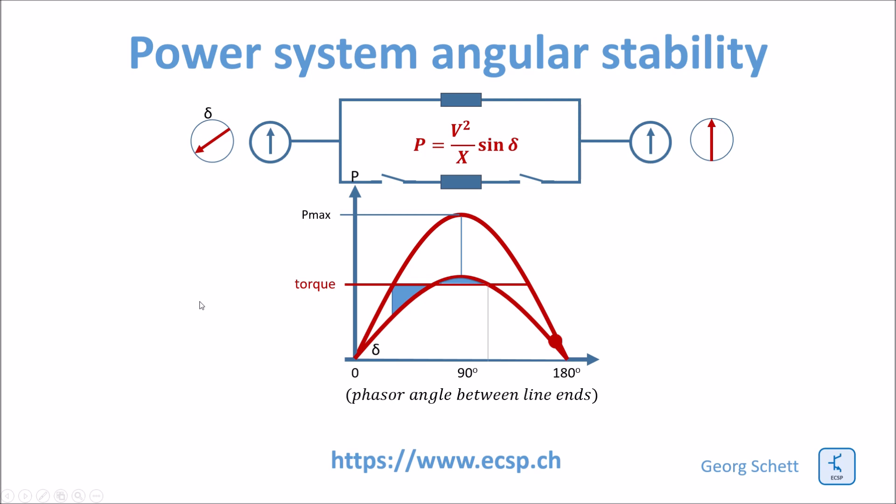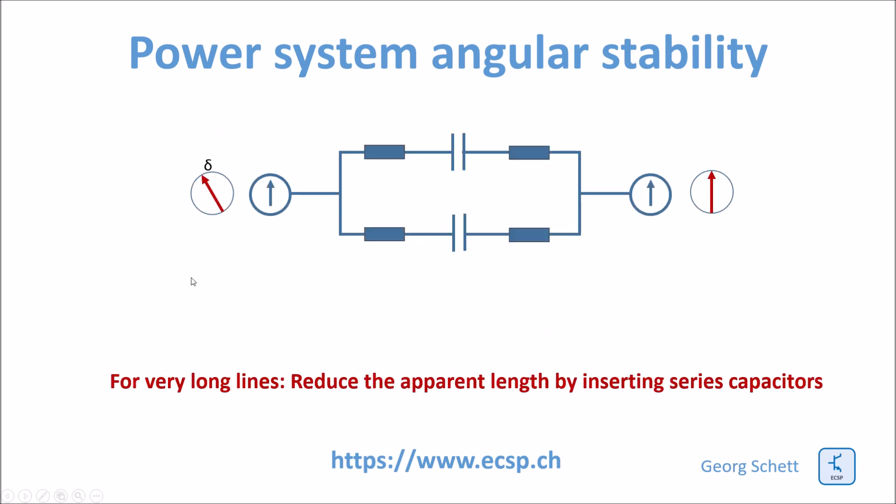So then you have very long lines of several thousand kilometers where this issue starts to play. And the point is that in order to keep the system stable under all circumstances, we can either increase the number of lines in parallel, or we can reduce the power to be transmitted, or there is another trick. What you can do is artificially reduce the apparent length of the line by adding some series capacitors to the system.